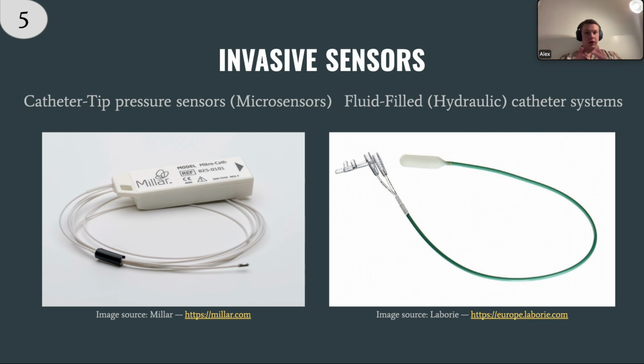Also, we can say that there are two major types of these sensors. The first type is catheter tip pressure sensors, microsensors. You can see it in the picture. Basically, it is a device with a sensor at the tip that goes inside the patient's body, and it catches the blood flow. Then the sensor turns it into an electrical signal, and there is a machine, this white box in the picture, and it shows us the blood pressure in real time.